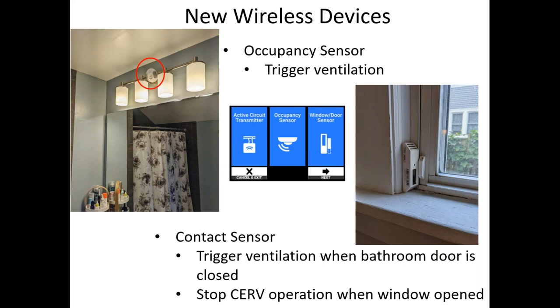So humidity might trigger it versus using the restroom. That may be triggered in a different way, because obviously humidity would not trigger it when you're just simply using the toilet. Contact sensors can also be used for triggering ventilation. If it's attached to a door, anytime that door is shut, it could tell the CERV to ventilate. You can also use these to stop operation. So if you like to open windows, you may have one on a window that you commonly open, and then you could have the CERV stop operating whenever you have the windows open.